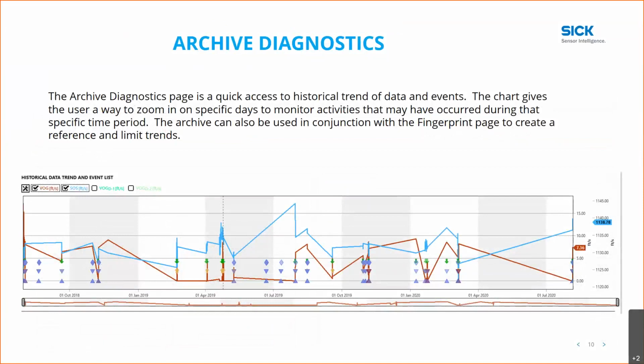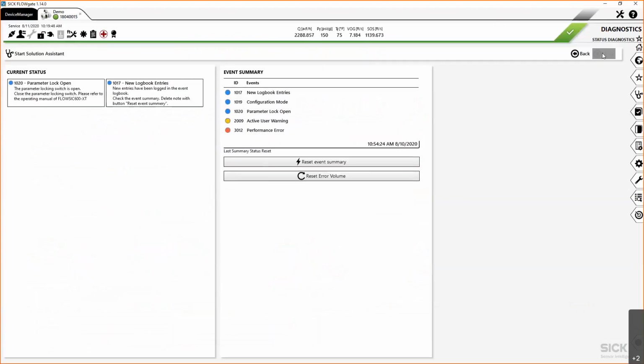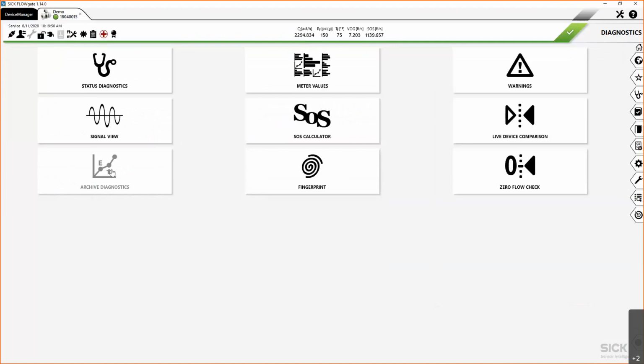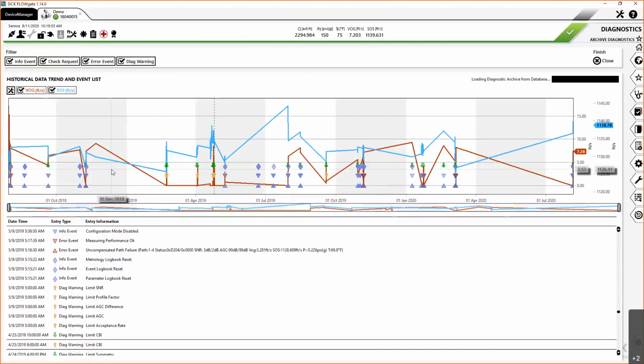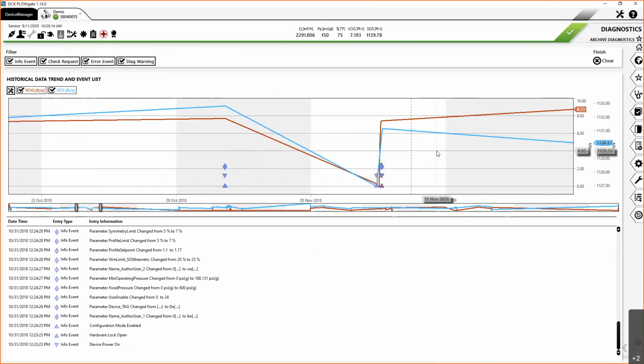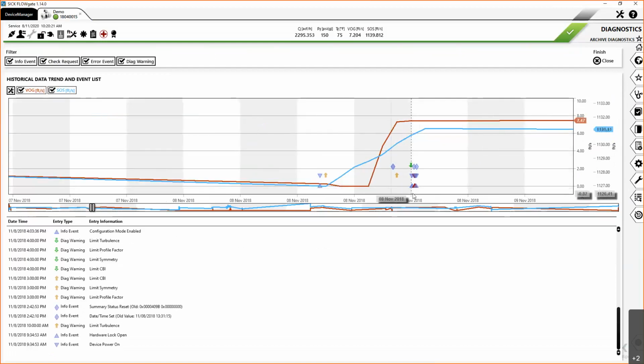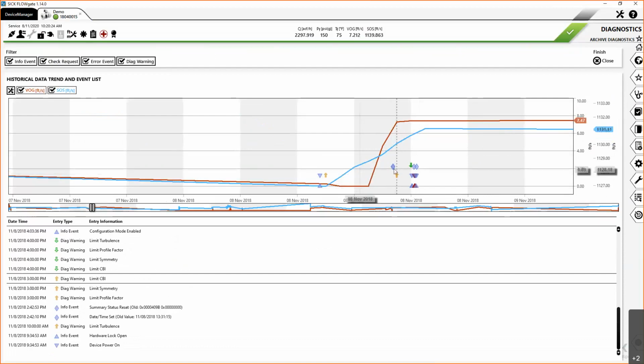Archive diagnostics is also available, going back to this meter here. You see, here's our archive diagnostics. The archive diagnostics gives you the whole history of any events, errors, or warnings that occurred in the meter since it was plugged in. I can zoom in on a specific area, such as here, and look at these particular dates, and then I can zoom in even further. I can see here's a warning that occurred, and if I click on that yellow arrow, it comes down to the bottom and tells me that my CBI limit was exceeded on that date and time.